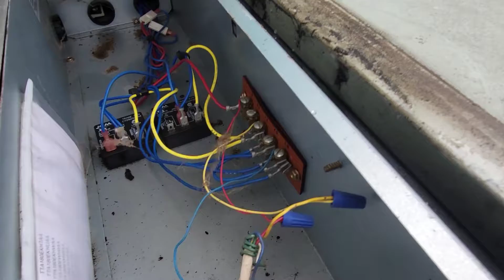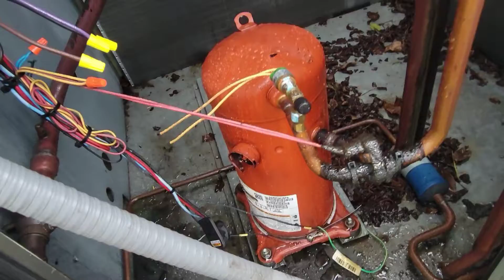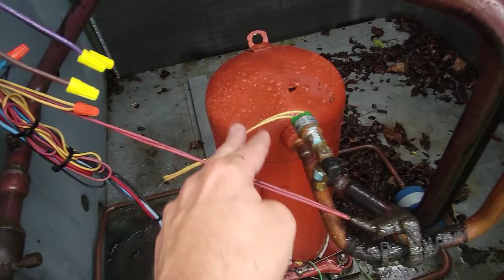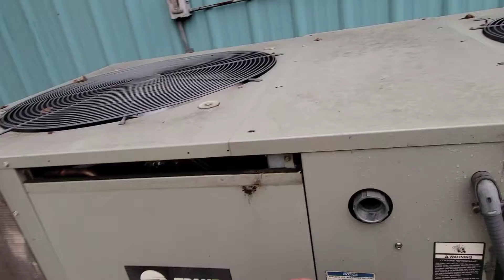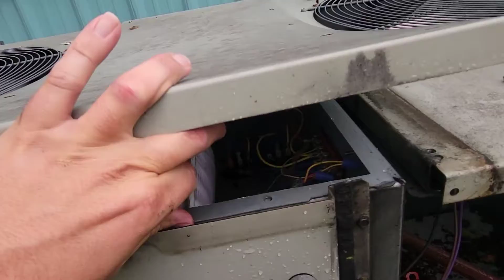Now, this is where I had to come next. And I had to make sure that my Y1 was wired up and not my Y2, because I don't need my Y2 anymore. You can see how I've taken the plug off, I've disconnected the fan wires, I've jumped out my high pressure switch and my low pressure switch because we're no longer using this side in this circuit, okay? And now I'm going to show you what I did with the contactor, because I had to do something to isolate the contactor.